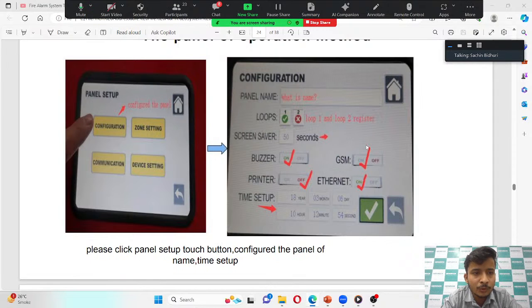For the configuration, after login, you need to go to the configuration. There you can set the panel name and how many loops you want to activate. You can set the screensaver timing, buzzer on/off, and printer on/off. You can enable and disable the GSM port, and enable and disable the Ethernet port. After all these settings, click on the right button, and all the settings will be stored in the panel.